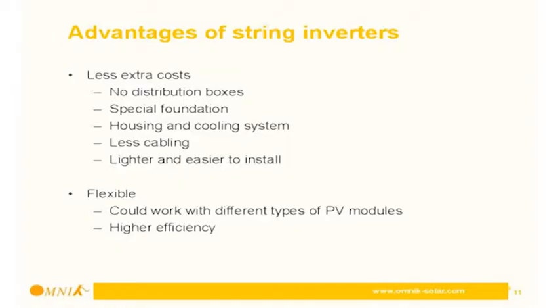About the advantages of string inverters, obviously there are fewer extra costs. We don't need any distribution boxes. We can just put it on the back of the panel, so there is no need for special foundations, housing, or cooling systems. There is also less cabling, because normally the string inverter will be very close to the panels, and it will be lighter and easier to install. We will go into more pictures later to make it easier for you to understand. And the string inverter is very flexible for installation design. It can work with different types of PV modules, which is the biggest advantage of string inverters.